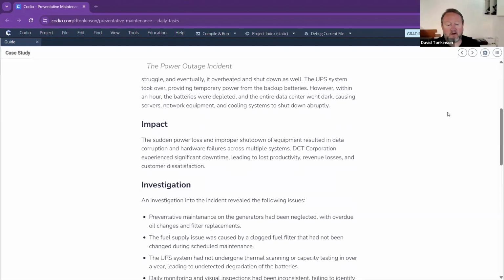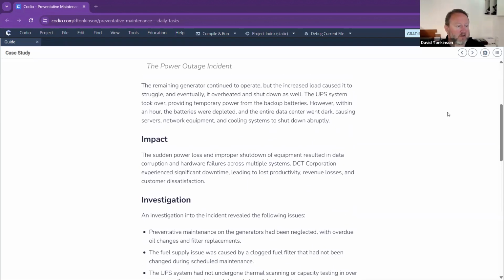Okay, so when I look through what they've got, oh, here we go. Patrick's now adding in. Patrick, root cause. Oh, here we go. Yinka. Yinka's nailed it. Thank you very much, Yinka. I'm going to read Patrick's first, Yinka. Patrick says root cause could be said to be the exciting incident of the thunderstorm and the fail of the utility power, essentially out of the DC's control. Yeah, that's a good comment. Yeah, beyond that point, well-maintained data center infrastructure should be in place to handle the situation. I suppose the first link in the chain failure was the first generator fuel supply issue, definitely.